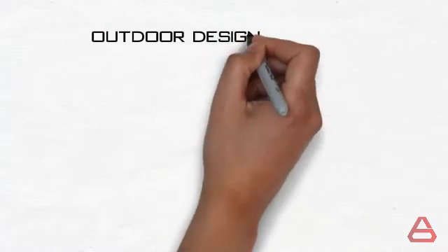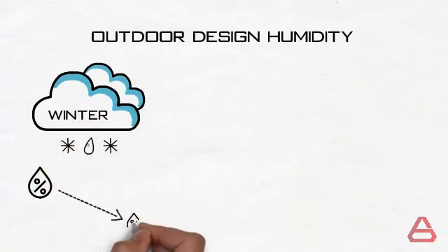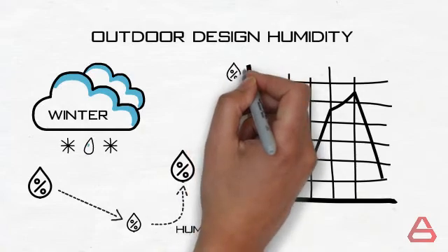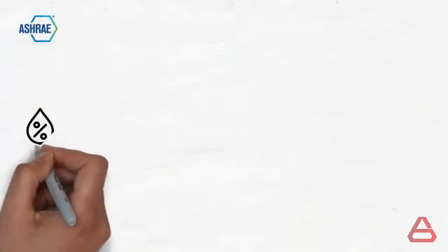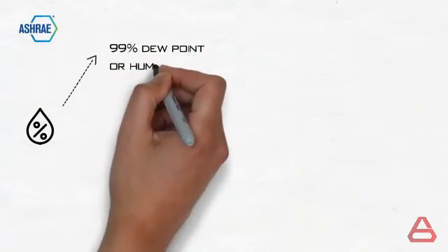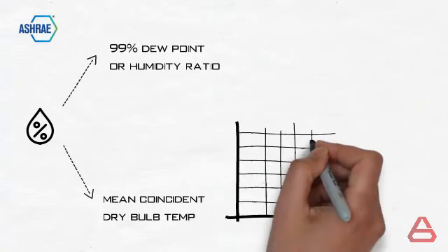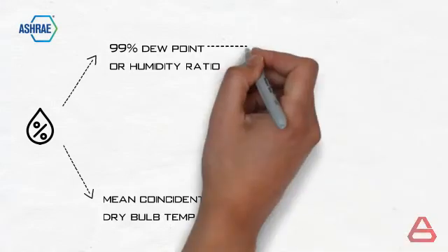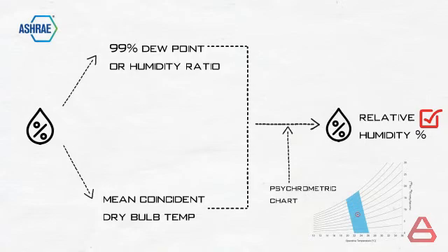So now that we have discussed temperature we move on to humidity and how we determine the outdoor design humidity. Humidity in the winter for homes and houses generally would require humidification. Therefore our outdoor design humidity should be one of the low humidity values recorded. The same 99th percentile applies here as it did in the dry bulb temperature part. ASHRAE offers the humidity value through providing the 99th percentile of the dew point temperature or humidity ratio and mean coincident dry bulb temperature. They provide the mean since the similar value of humidity has variable dry bulb temperatures. With the help of a psychrometric chart you can determine the outdoor relative humidity and there you go.